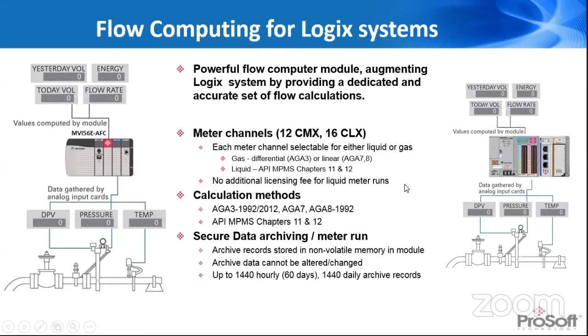The Windows-based software, like I mentioned: measurement divisions have to be able to do certain functions related to measurement, and they don't necessarily want a Studio 5000 license. A lot of times your measurement and your automation groups are still separate groups, and the automation guys don't necessarily want the measurement guys going into the PLC and making changes. So this software allows measurement groups to make whatever changes they need for gas analysis, orifice plate, and enter meter factors, basically set up and configure the measurement related functions independent of Studio 5000. Like I said, it's a coprocessor that sits in the rack that performs measurement related functions.